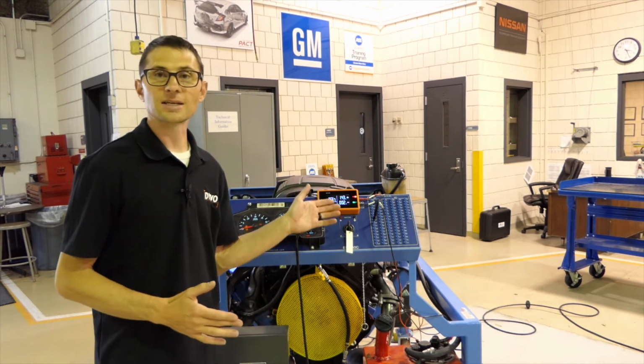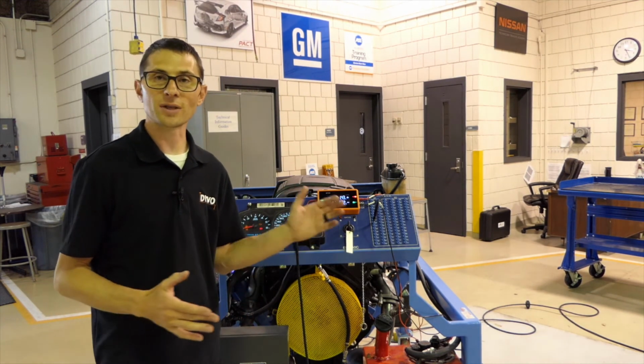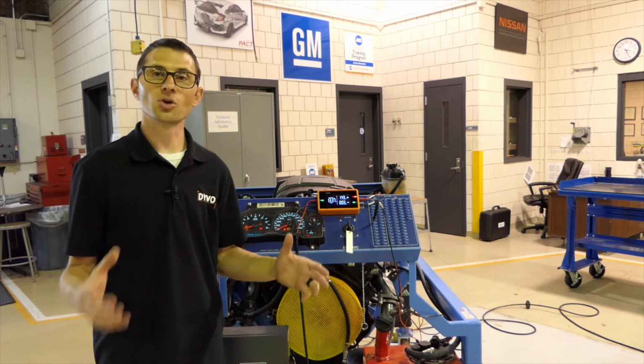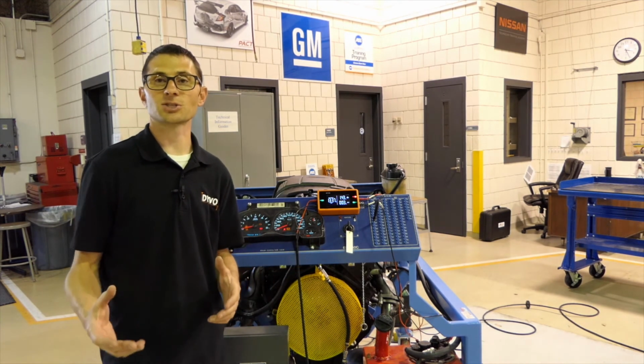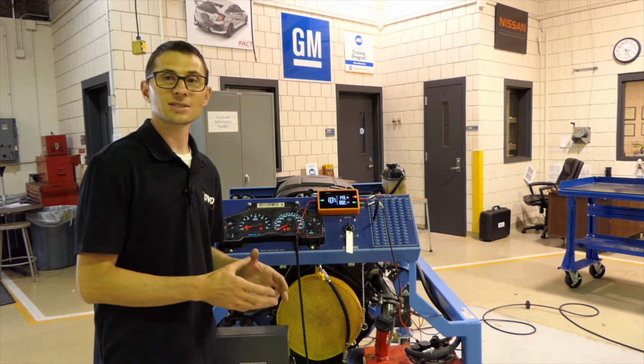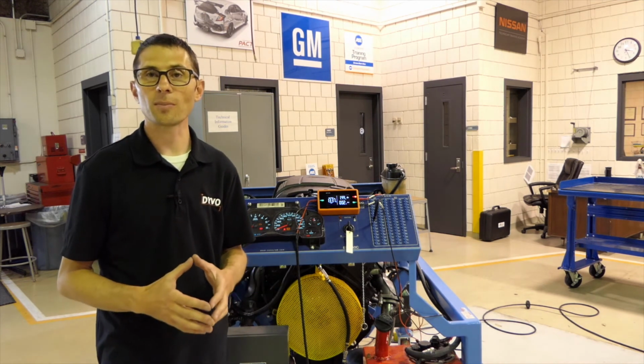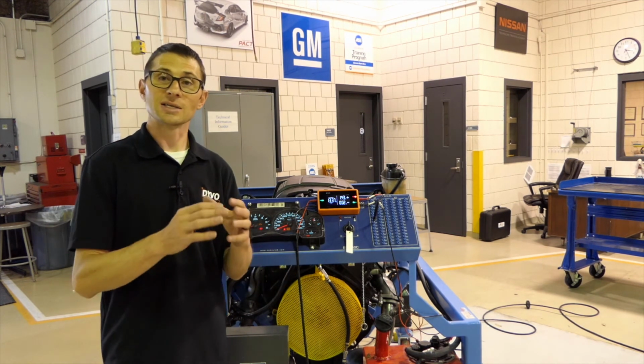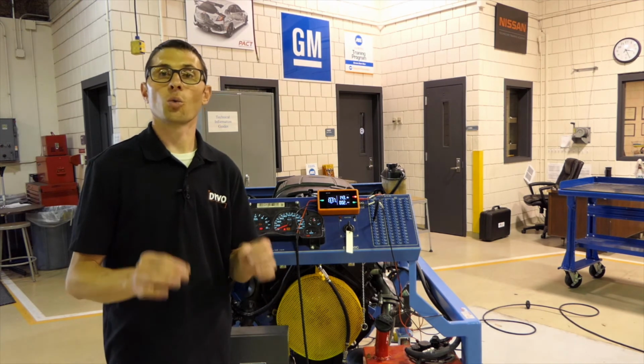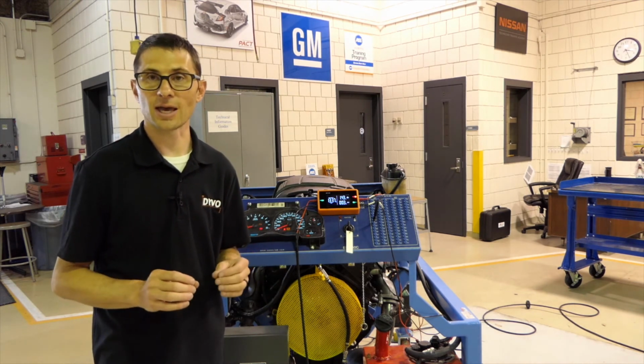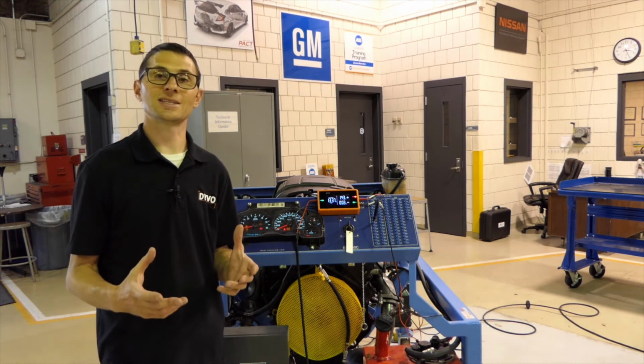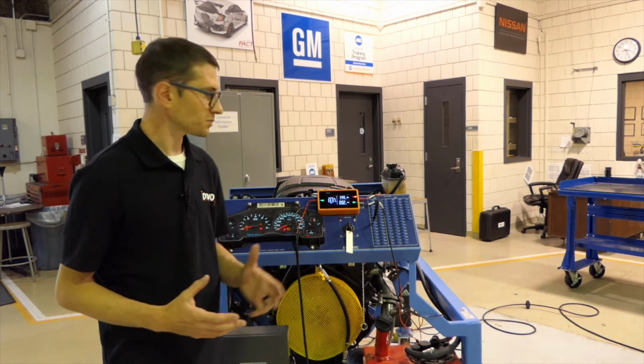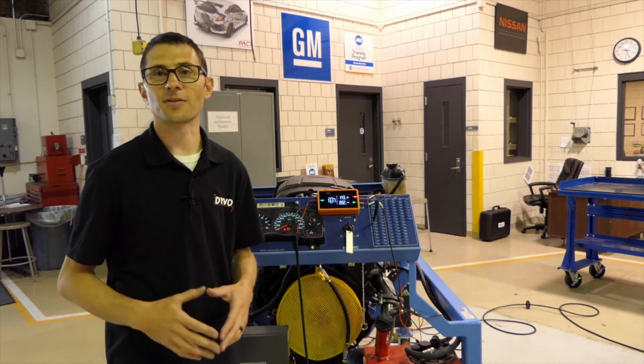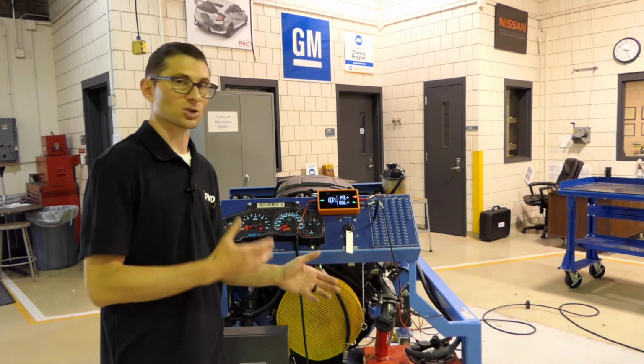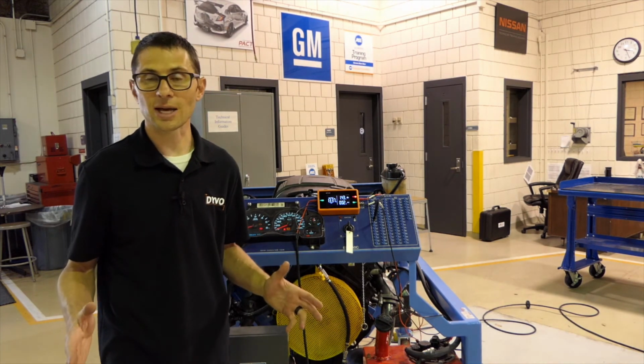We have already identified that there is a wiring issue between the sensor and the control module. There's no reason to take additional steps to test resistance. And the resistance test isn't going to be as accurate. Remember that a resistance test will show you 0.00 ohms with just one strand of wire holding it together. So it will show a good connection when indeed we don't have a good connection. Here we've easily identified that there is a wiring issue between the sensor and the control module. No additional steps needed.